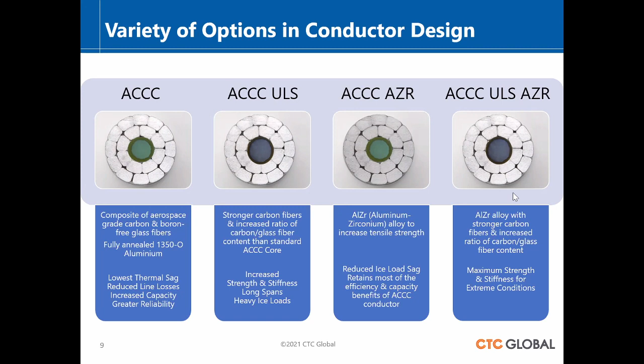This ACCC was the very first conductor and currently the only conductor that has been third-party certified as reducing CO2, mostly because it's just more efficient, reduces energy, and the energy related to that CO2. So across 5 scenarios, they tested it and confirmed from 27 to 31% lower carbon emissions as a result of using this in place of the very same diameter and weight ACSR.